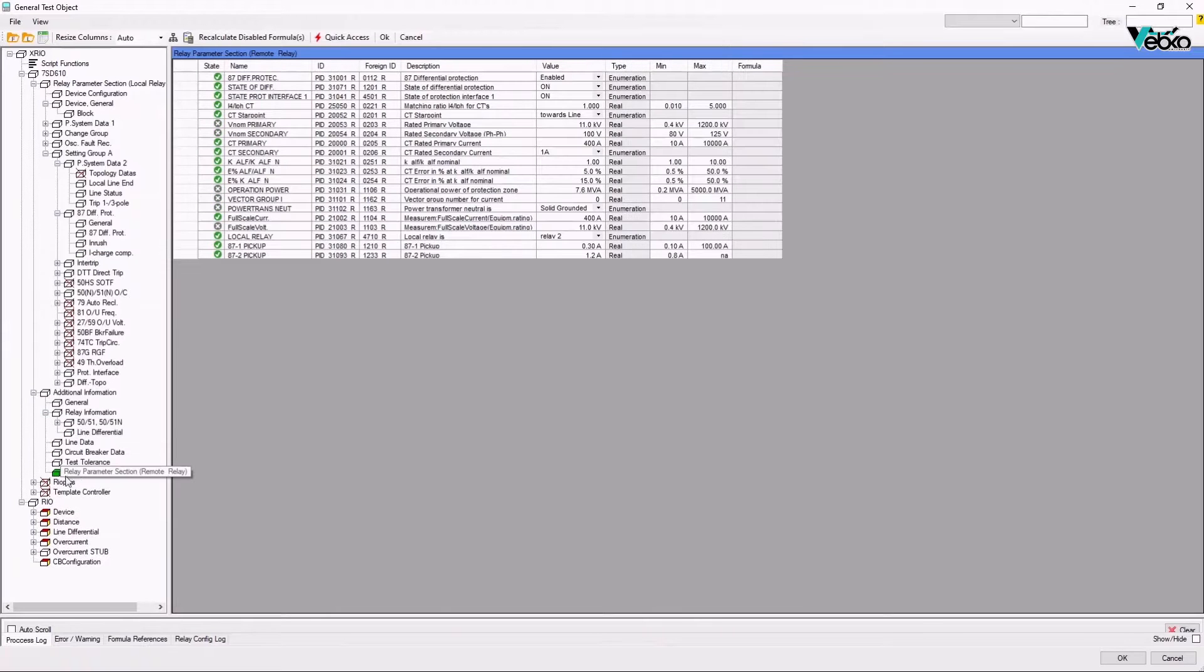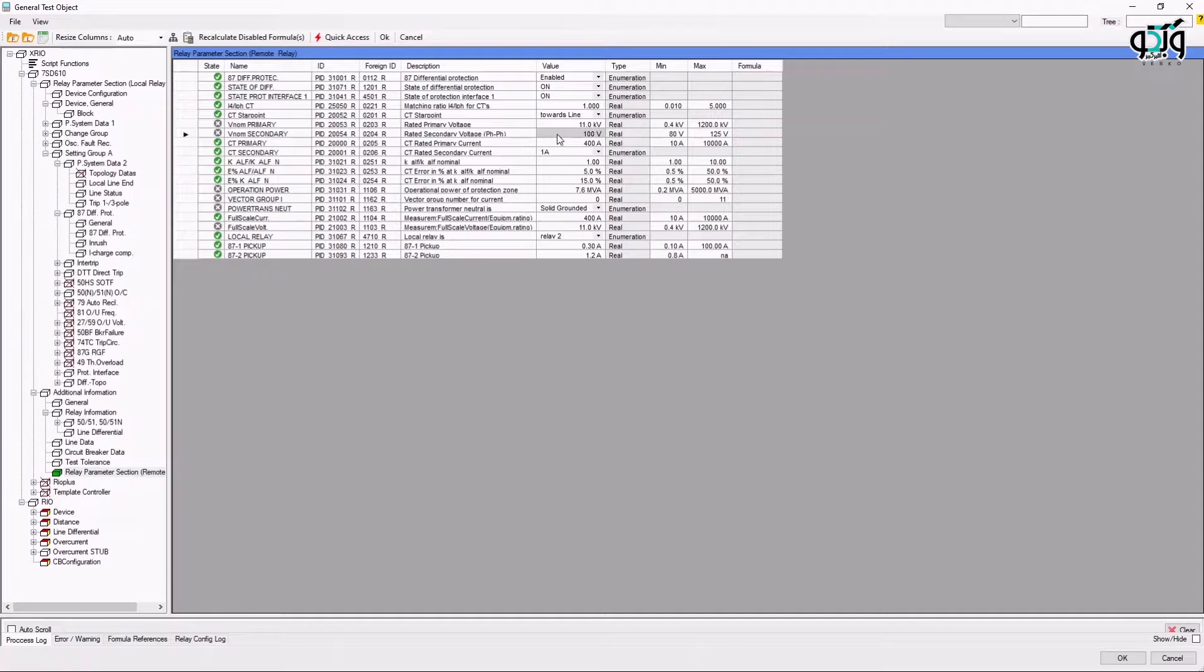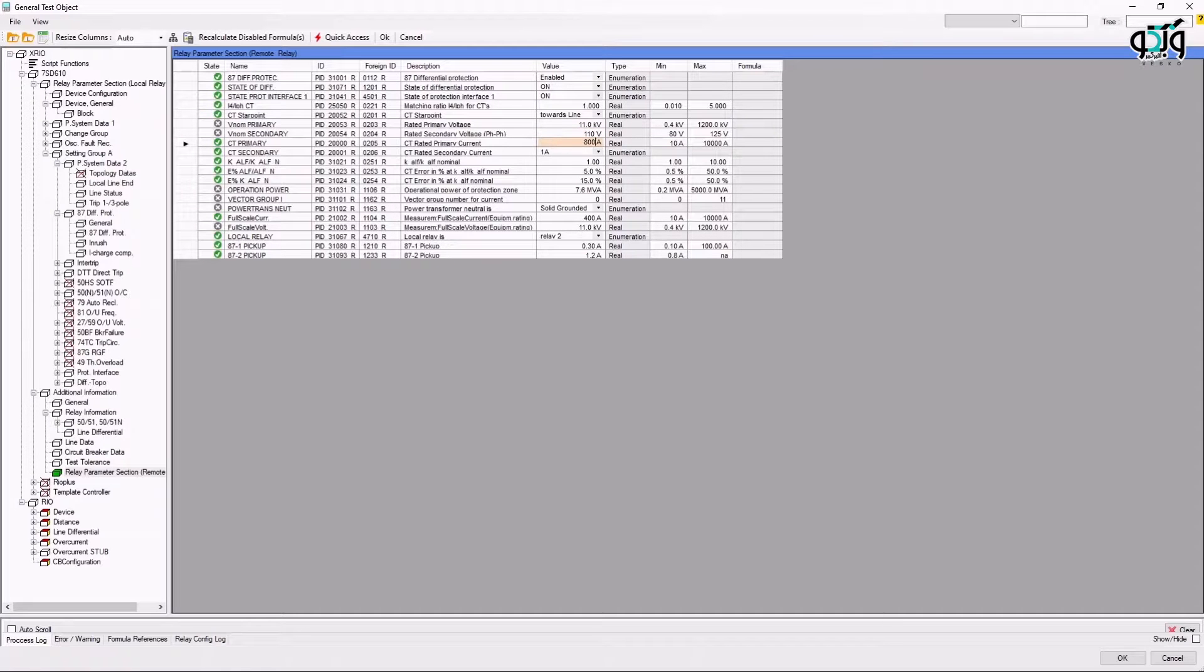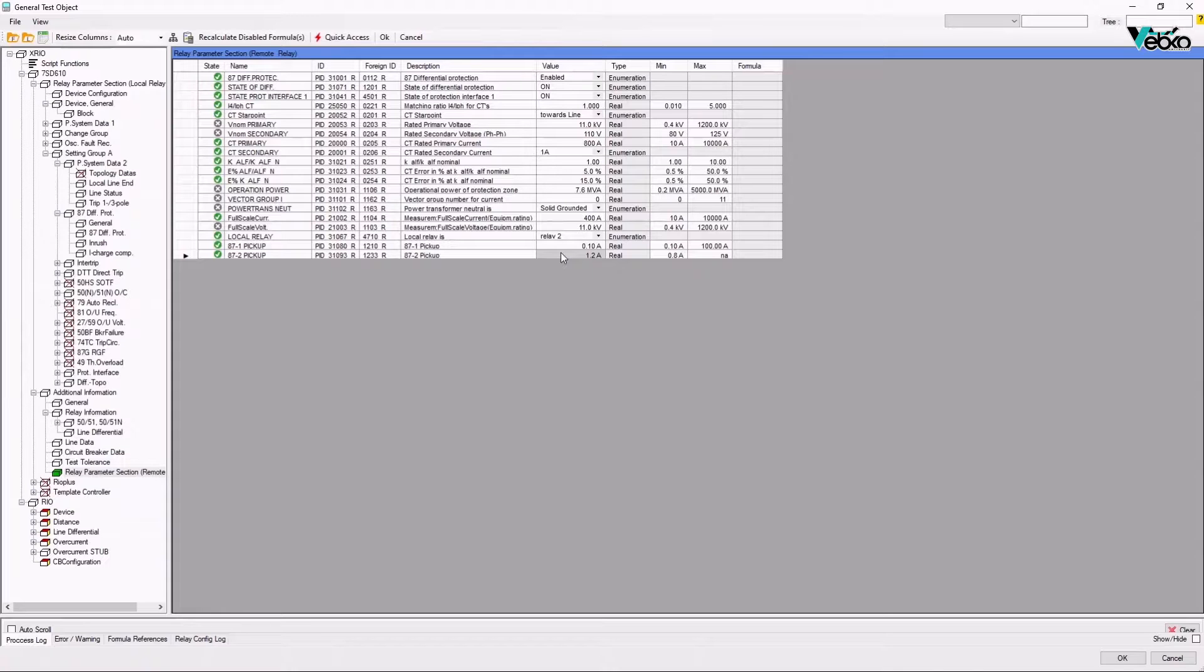In Relay Parameters section, it is possible to view the information related to the relay of the opposite post. Here, parameters with a green check mark in a state section in front of them are the elements that are active in the relay of the opposite site. In this section, it is possible to receive the information about the relay of the opposite site from the setting file, XML file or even orally from the operator of the remote post and enter it into the value field.